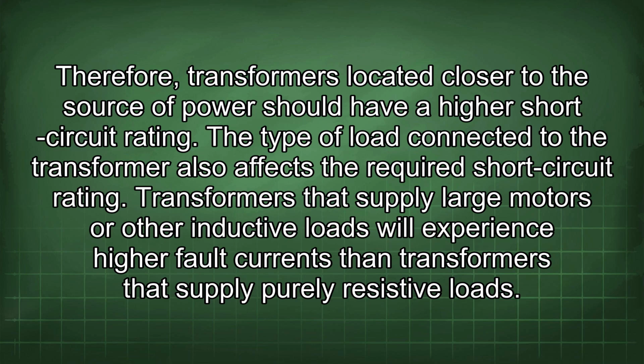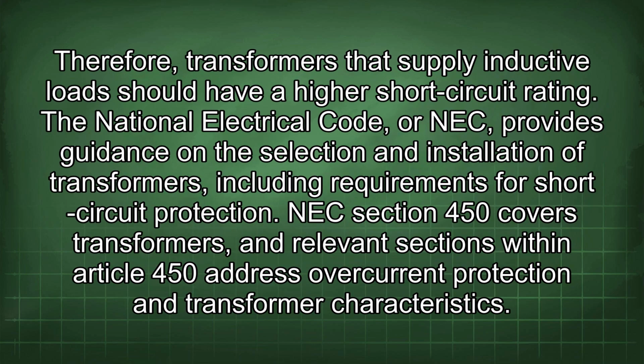The type of load connected to the transformer also affects the required short-circuit rating. Transformers that supply large motors or other inductive loads will experience higher fault currents than transformers that supply purely resistive loads. Therefore, transformers that supply inductive loads should have a higher short-circuit rating.